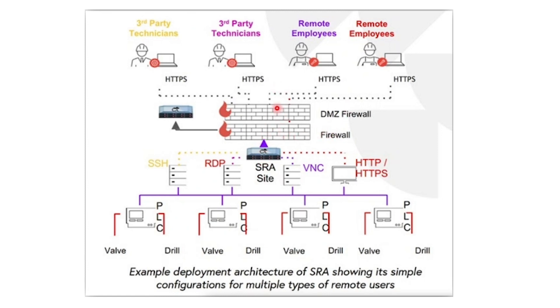All requests from a third-party technician or remote employee come to a DMZ firewall over VPN through SSL. Once the request is verified by the access server based on the configured policy, the communication is extended to the SRA site. Once the user has access to the SRA site, they can initiate SSH protocol to a PLC, RDP to an HMI, or VNC or HTTPS-type communication.